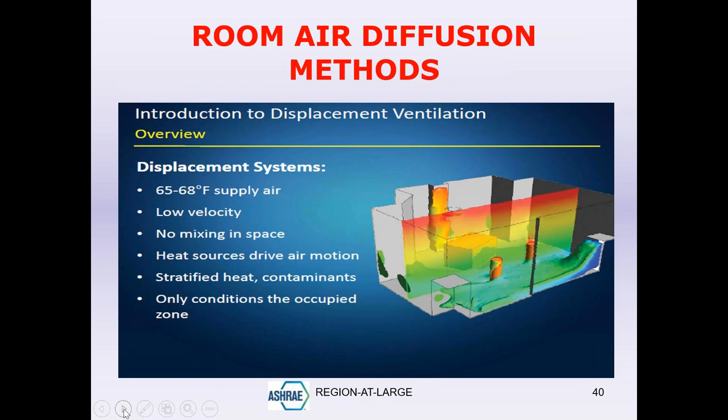In a displacement ventilation system, recall the three characteristics of a mixing air system: in mixing, primary air is supplied far away from the occupied zone. In displacement, the primary air is supplied directly into the occupied zone — units are installed within the occupied zone itself, not overhead or on a far sidewall. And since the outlets are located within the occupied space, the supply air temperature must be higher, typically between 68 to 70°F, rather than the 55°F used in a mixing system.